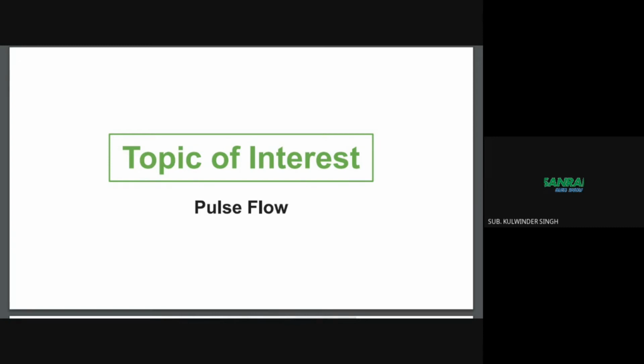So talking about the pulse mode, it goes by many names: pulse flow, on demand, intermittent flow, oxygen conserving device, or puffer. Actually, a pulse flow puffs or pulses oxygen into the patient's nose through a cannula with each breath. Whenever the patient triggers or initiates a breath, then it delivers the breath. This means oxygen is delivered only during the inhalation phase, and the device stores the oxygen when the patient exhales. If the breathing rate increases or decreases, the POC will adjust the pulse size and the delivery frequency of the breath to maintain the required flow rate.